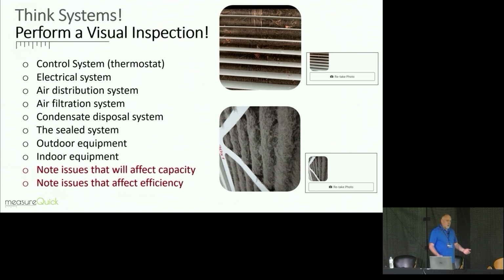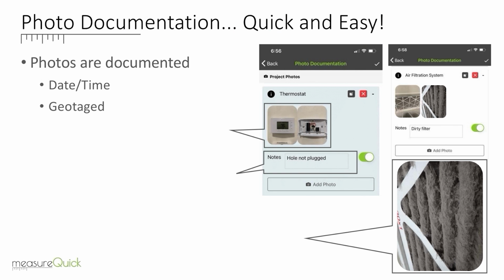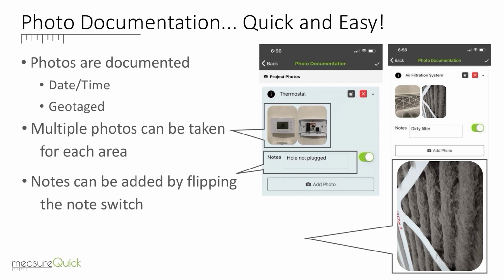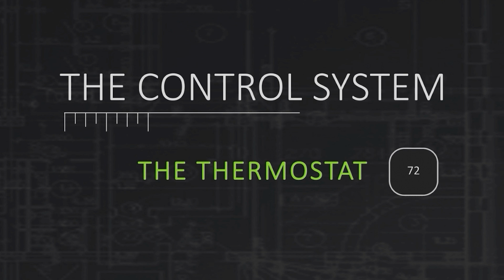And here's the issue. We have people every single day connecting MeasureQuick to systems, and they can't figure out why it's giving them flags on the system, why they're getting an airflow flag, a charge flag, a capacity issue. They're missing those issues because they aren't looking at it from a system approach, right? So anytime during this commissioning process, we have a photo documentation section built into MeasureQuick. And you can document as you're going through this visual inspection, take photos of that and take notes. You can add notes by flipping the note switch on, and then you can tap the photos to view them full screen. But this is a pretty valuable part of using MeasureQuick, actually photo documenting what's wrong with the system. So let's start out with the control system.